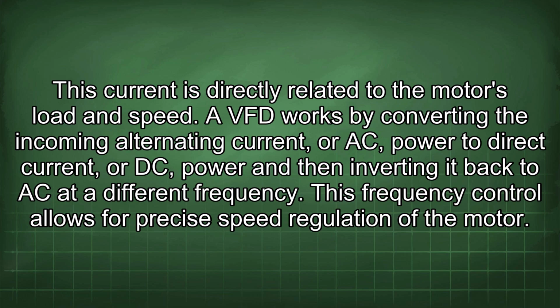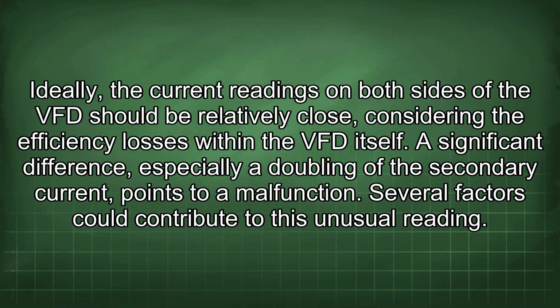A VFD works by converting the incoming alternating current, or AC, power to direct current, or DC, power, and then inverting it back to AC at a different frequency. This frequency control allows for precise speed regulation of the motor. Ideally, the current readings on both sides of the VFD should be relatively close, considering the efficiency losses within the VFD itself. A significant difference, especially a doubling of the secondary current, points to a malfunction.